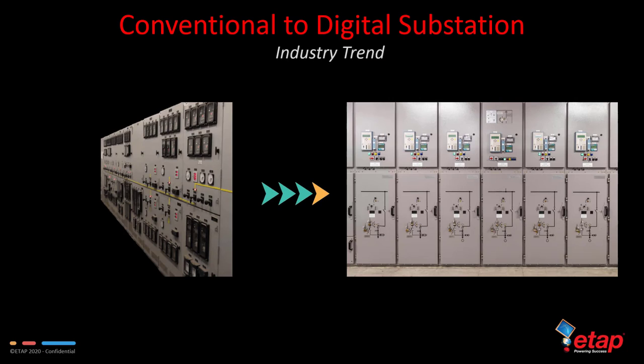As we know, power system protection emerged at the beginning of the last century with the application of the first electromechanical overcurrent relay. The majority of the protection principles currently employed in the relays were developed within the first 3 decades of the last century, such as overcurrent, directional, distance, and differential protection. In the last century, from the emergence of protection to the end of the 1990s, relay protection has undergone a number of development stages thanks to digital transformation and digital substations, migrating from electromechanical to semiconductor and subsequently to integrated circuit and microprocessor technologies. Today, microprocessor-based digital and numeric relays are replacing conventional relays in all areas of power system protection, and that's one of the industry trends.